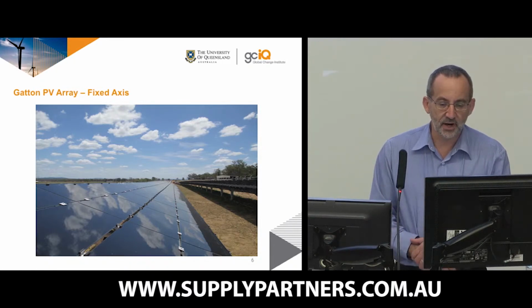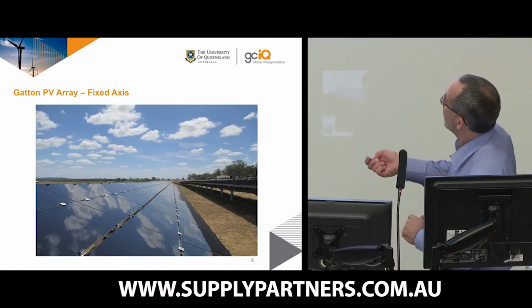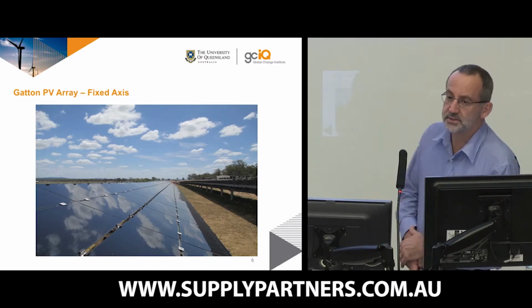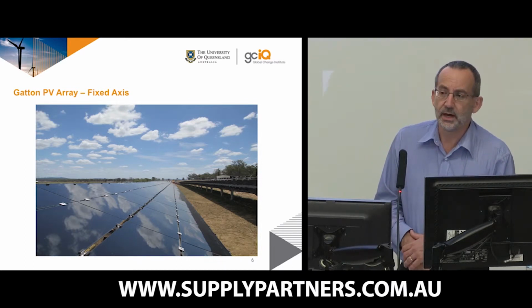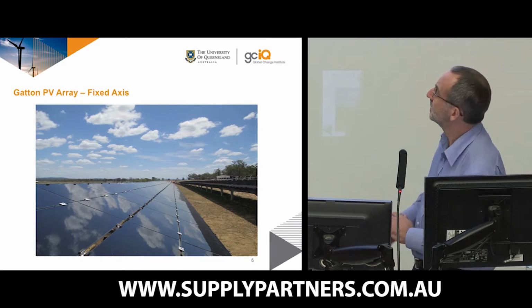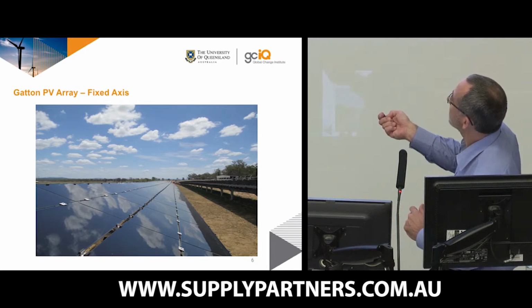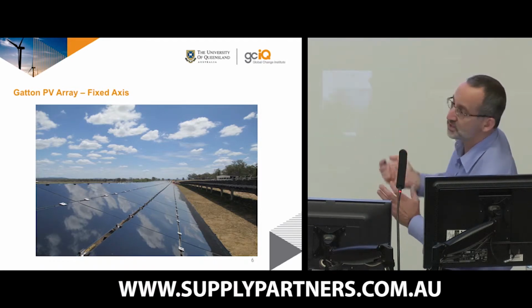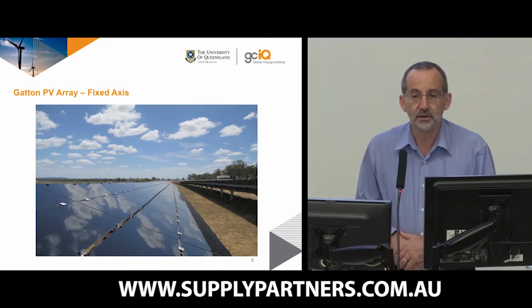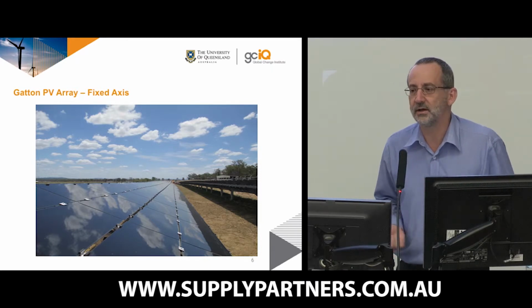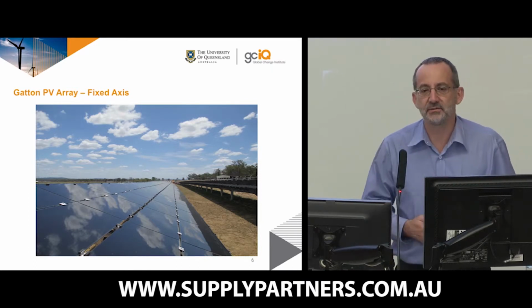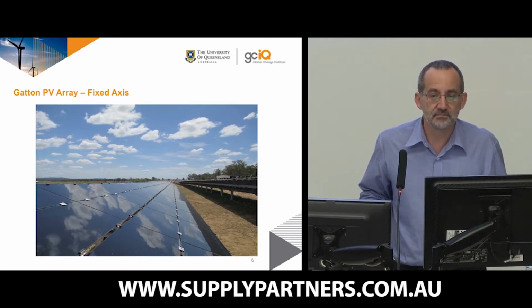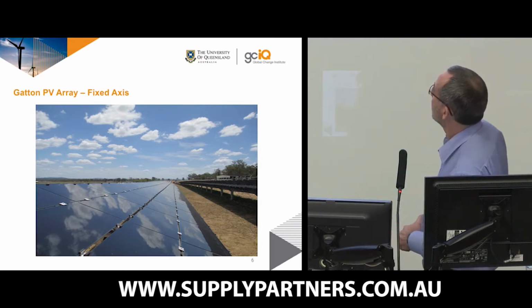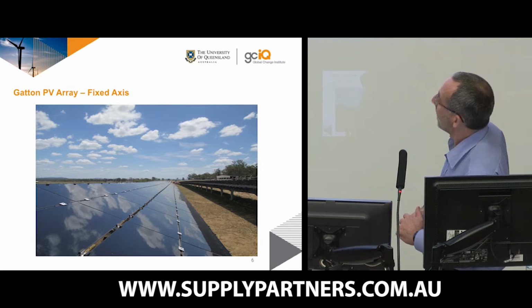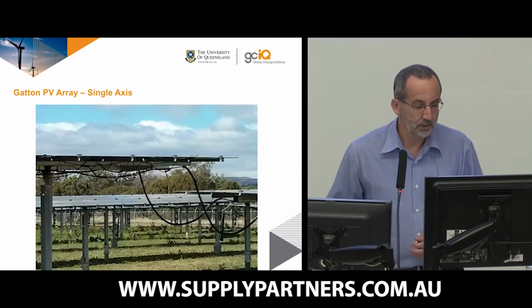That's the fixed axis arrays close up. The panels are all thin film, so they're only 95 watts each, with thin film cadmium telluride. It uses galvanised piers into the ground. I'll show you a few details later on. There's a long beam along here, and each of those is about 200 metres long. One of the things you have to think about in a design like that is thermal expansion: that thing can expand by almost 4 inches, 90 millimetres or so. The panels are clipped in.